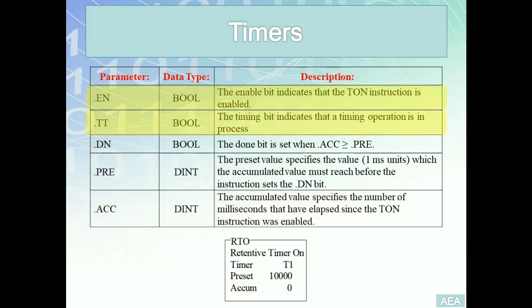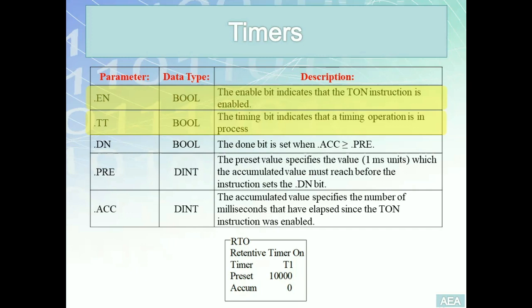The three Boolean parameters are the enable bit, timer timing, and done bit. The enable bit indicates whether the timer on instruction is enabled — the rung-in condition that triggers the timer specifies its state. If the rung-in condition is true, the enable bit is true; if false, it's false. The timer timing bit indicates that the timing operation is in process — when the timer is active and the accumulator is still less than the preset value, timer timing is on. The done bit is the flag indicating that the accumulator has reached the preset value.